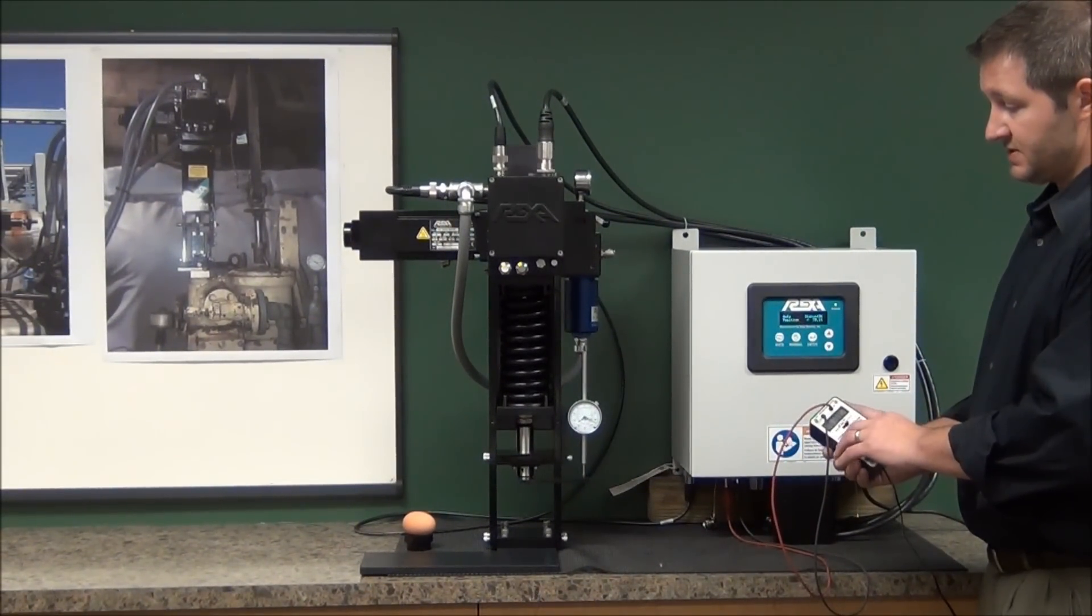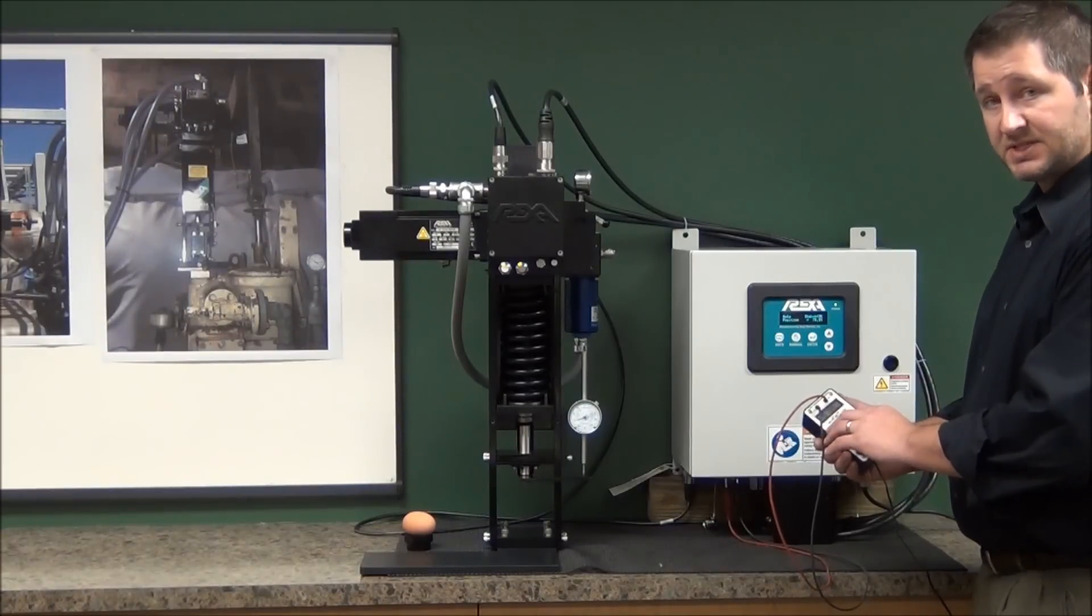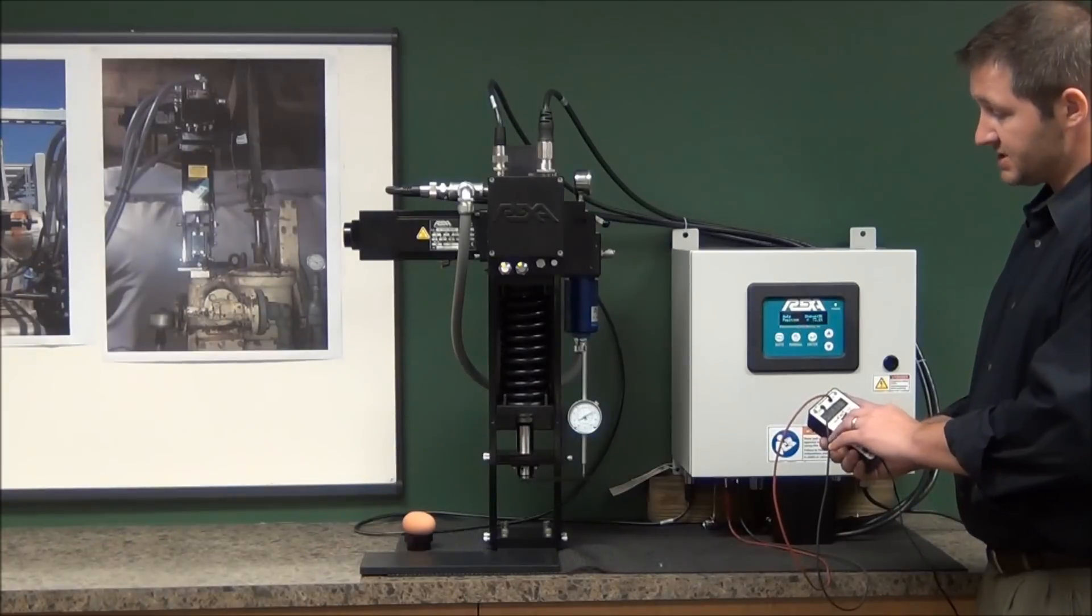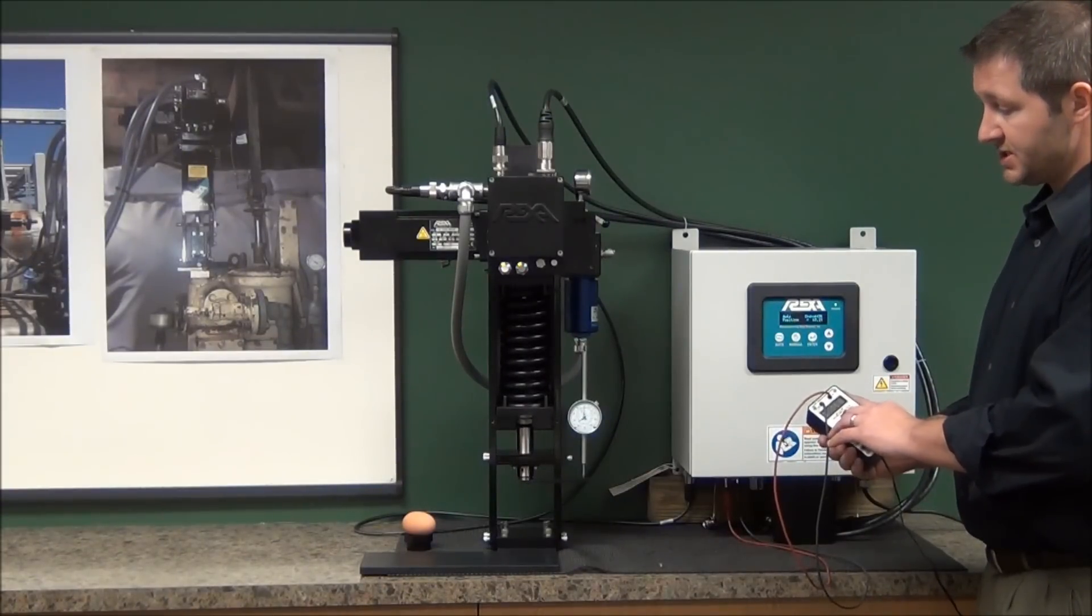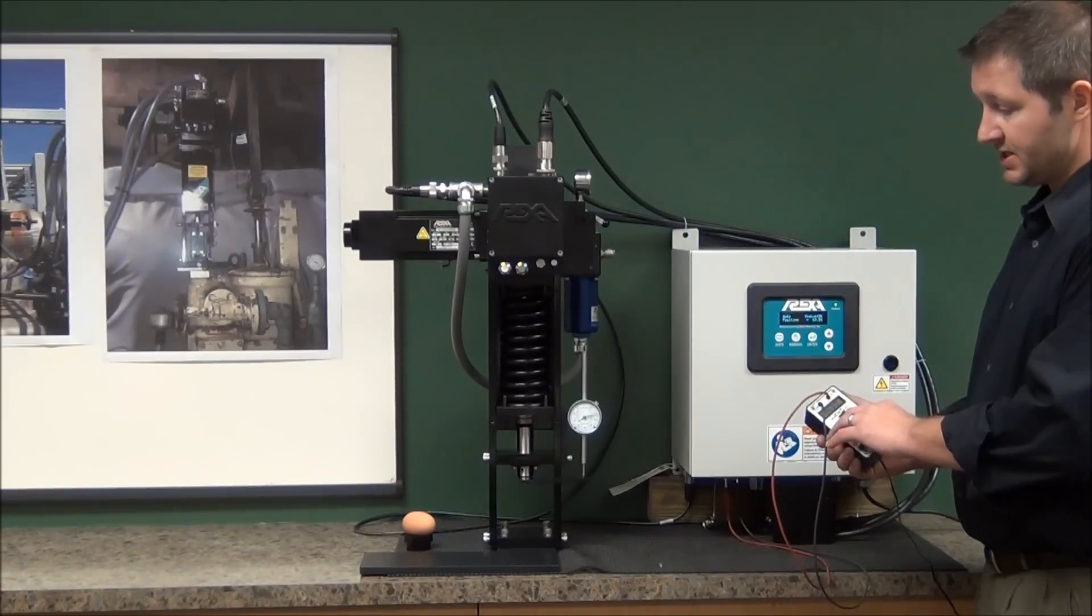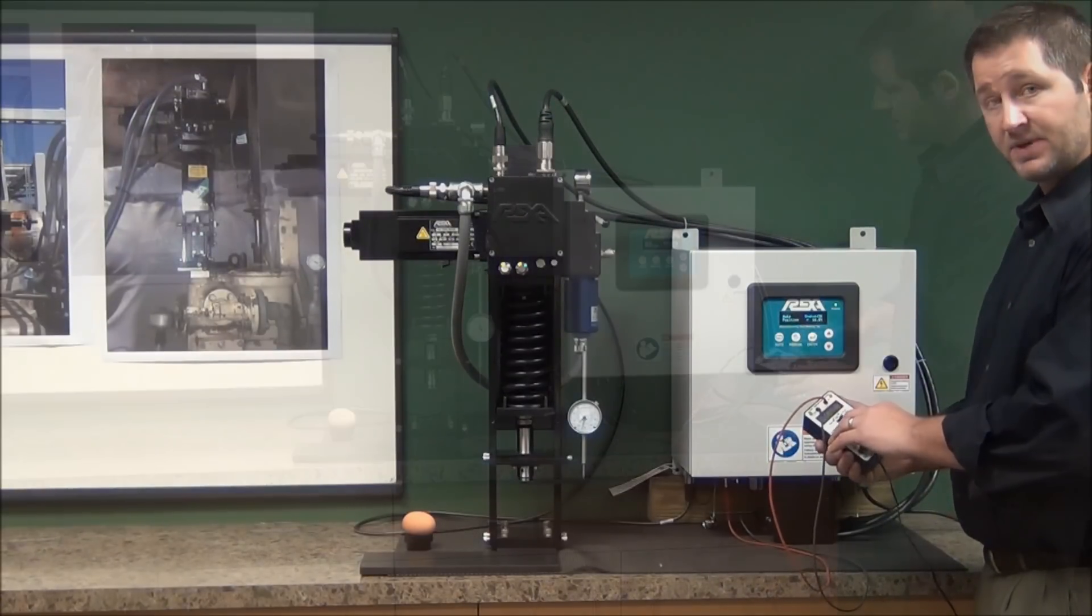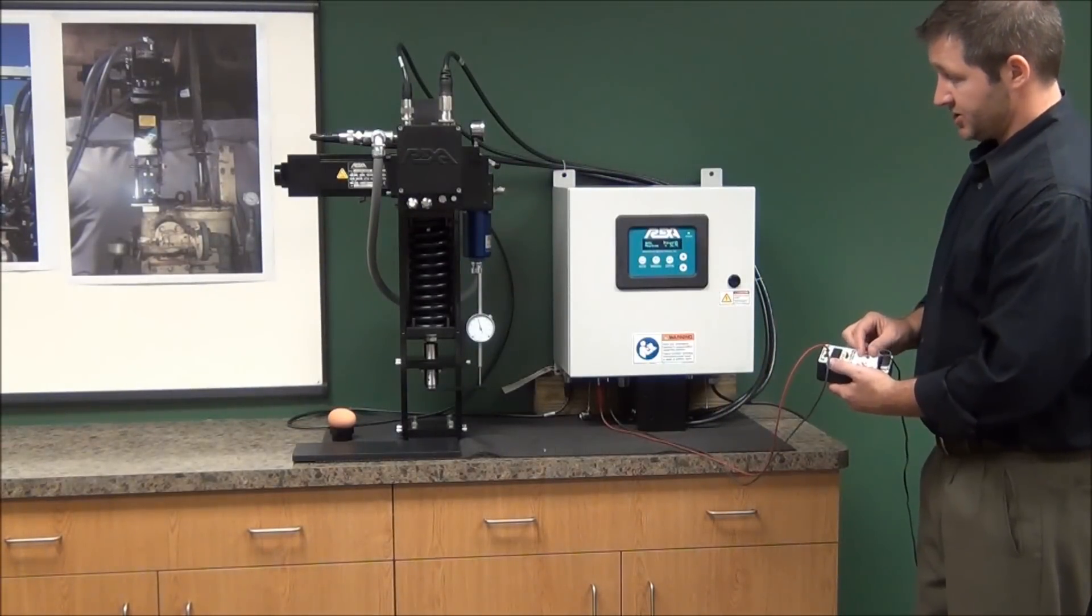The unit has a very short dead time, 70 to 80 milliseconds, a very rapid response. 100% duty cycle, so it can continuously position the turbine valve and maintain that RPM. So I'll demonstrate the actuator's fail-safe function.